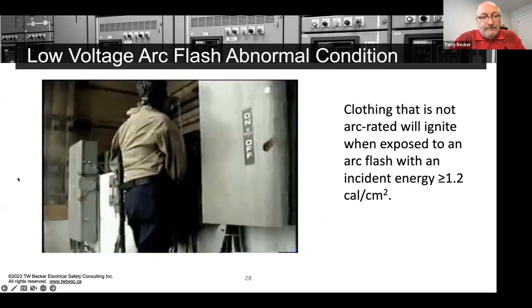Now some videos. This one I'm showing you because it shows that we need arc rated clothing on a worker doing arc flash risk work, because it won't ignite. In this case, it's a cotton shirt and the incident energy is greater than 1.2 calories. It's probably a 40 volt simulation of an arc flash, and the clothing ignites. So I'll just play the video.